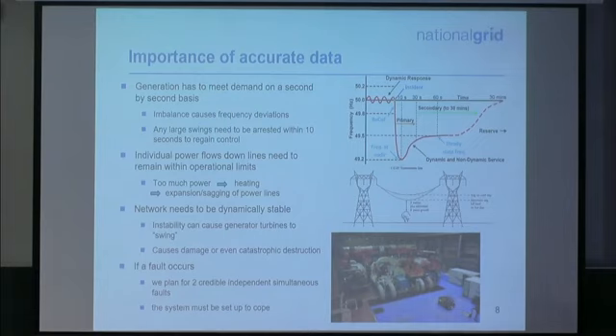If you don't have enough inertia on the system—electrical inertia generated by the actual spinning metal of the turbines, converting physical inertia into electrical inertia—then machines can speed up. Another machine in a distant part of the country senses that and speeds up too, while the first one slows down. You can get oscillations between different parts of the country, and those oscillations can grow with positive feedback, rattling the bearings the turbines sit on and significantly shortening the lifetime of the power station.